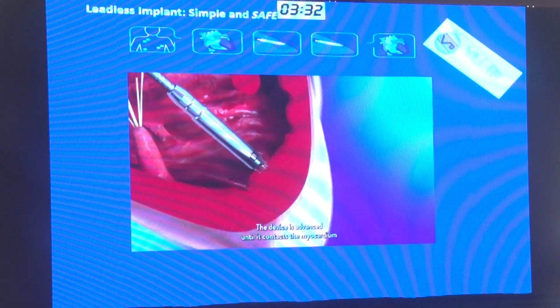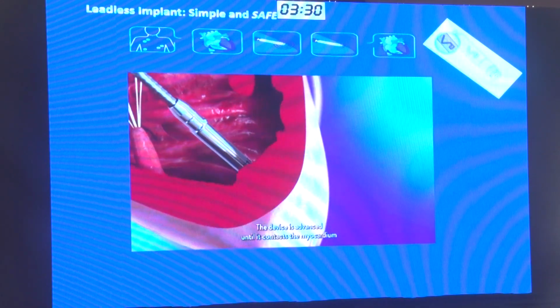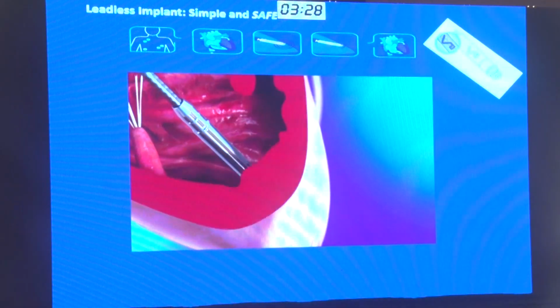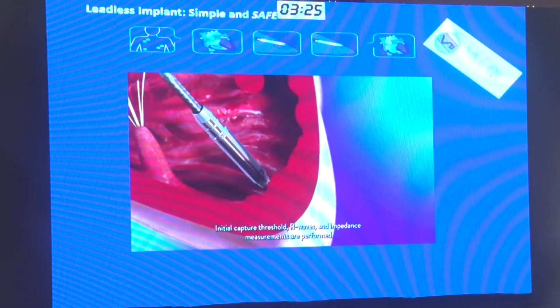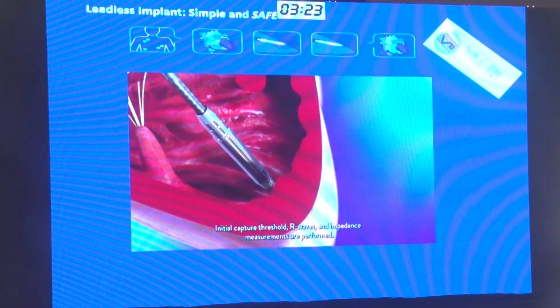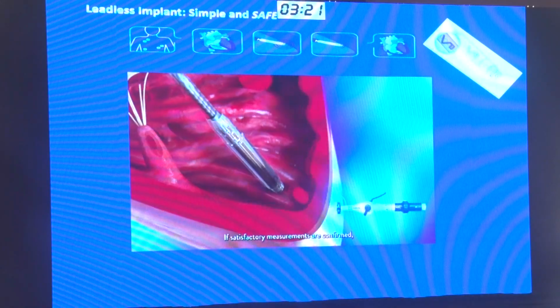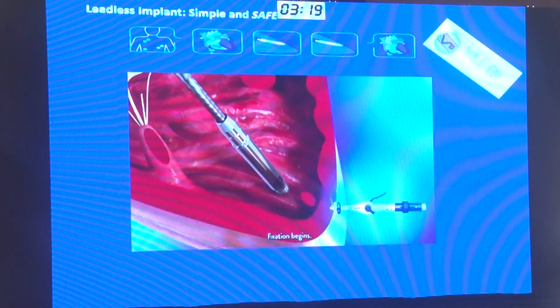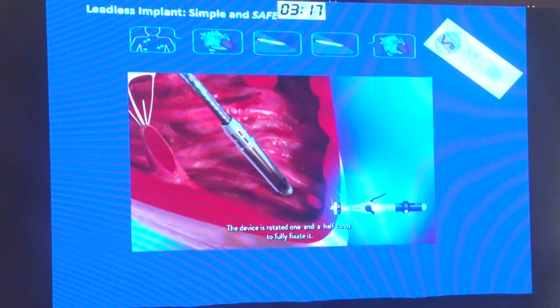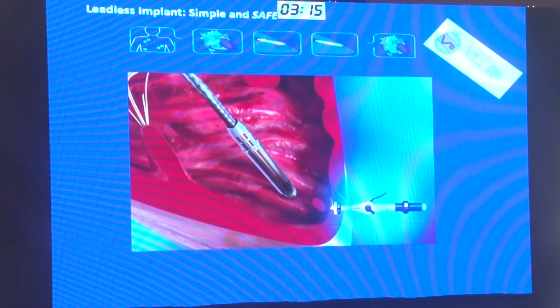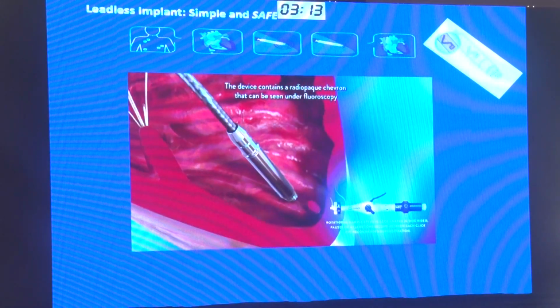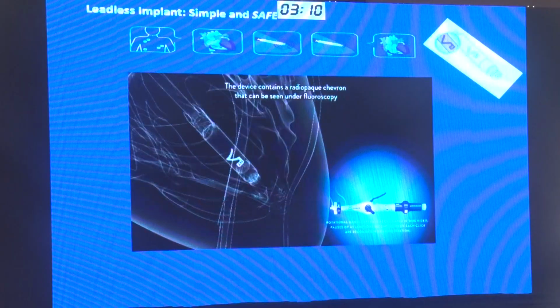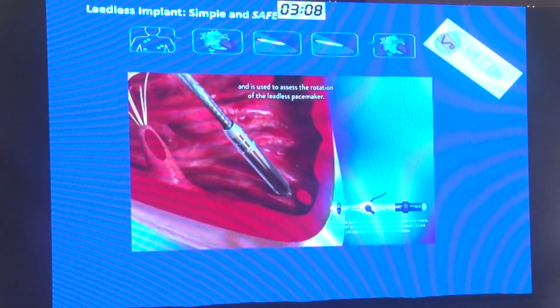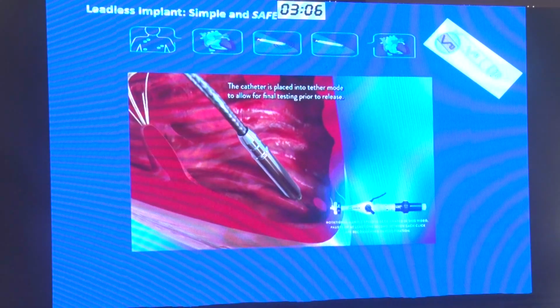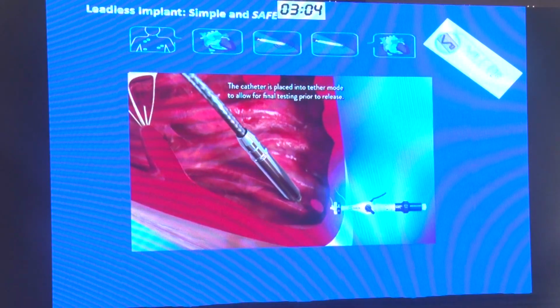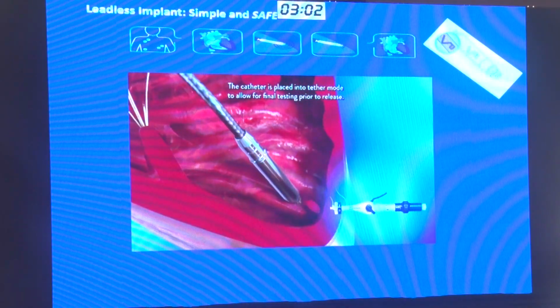The device is advanced until it contacts the myocardium to allow for mapping of the location. Initial capture threshold, R waves, and impedance measurements are performed. If satisfactory measurements are confirmed, fixation begins. The device is rotated 1.5 turns to fully fixate it. The device contains a radiopaque chevron that can be seen under fluoroscopy and is used to assess the rotation of the leadless pacemaker. The catheter is placed into tether mode to allow for final testing prior to release.